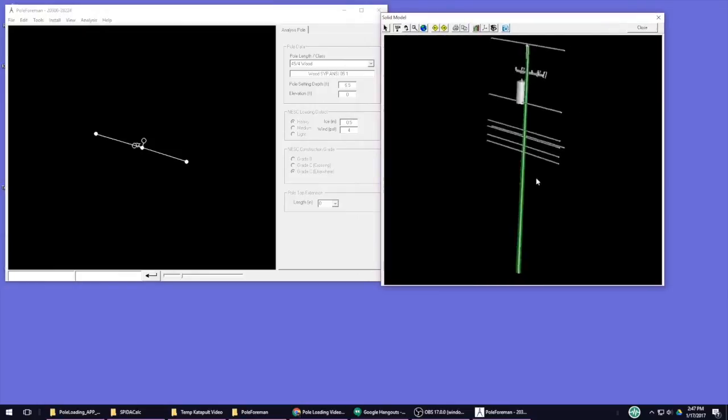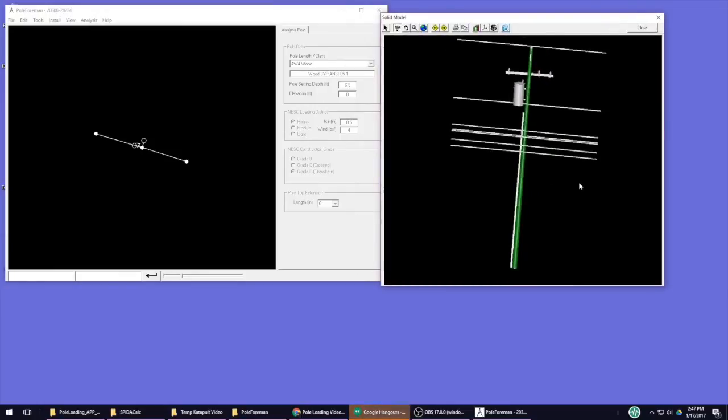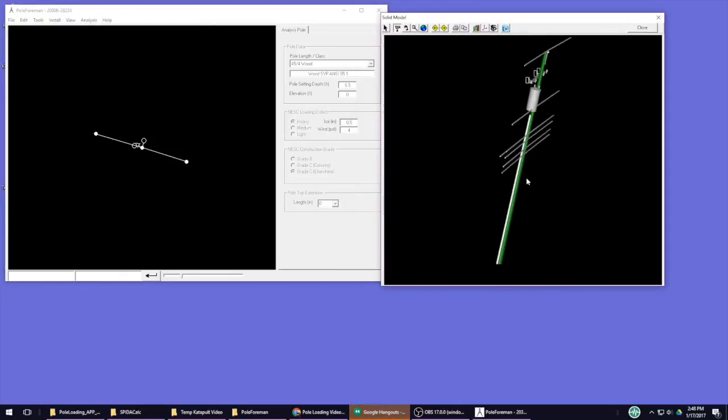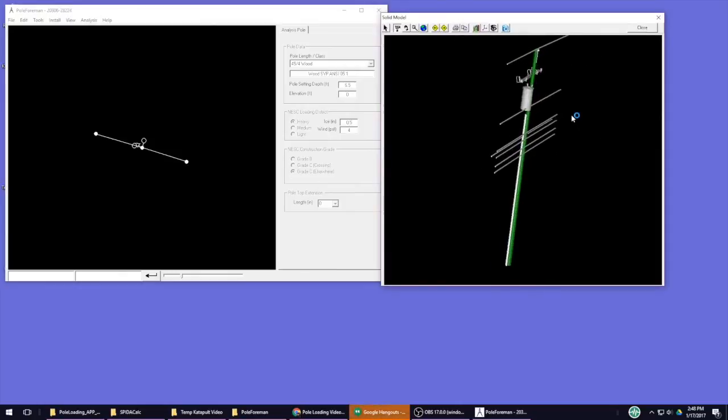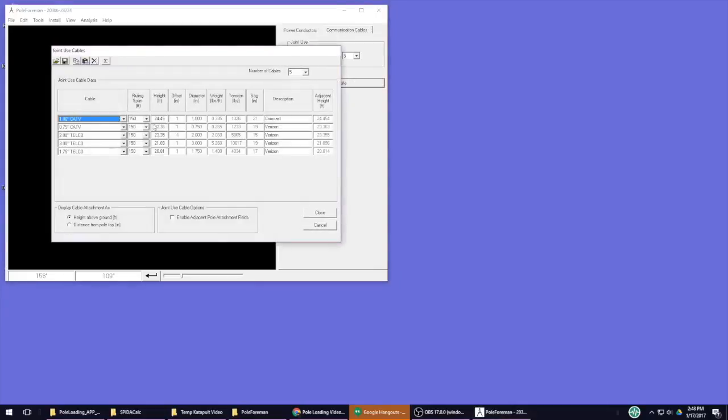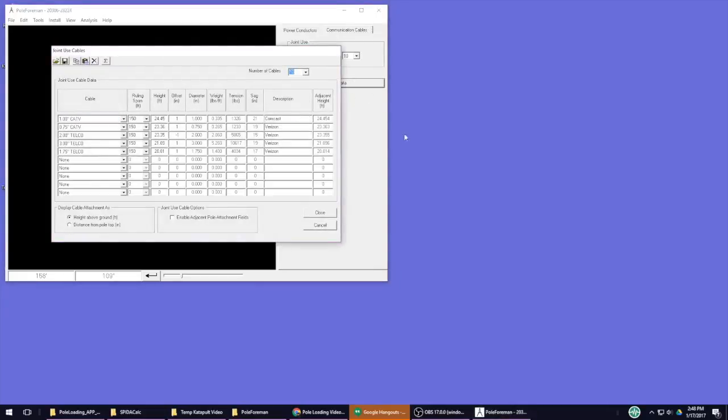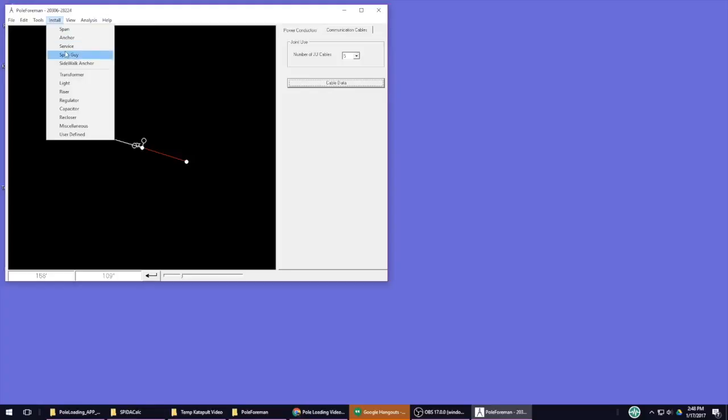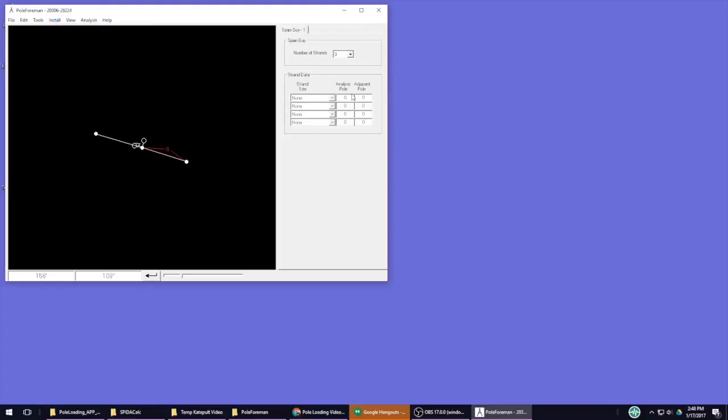Although the 3D model is great, the user cannot edit the pole and view the model at the same time. You have to alternate windows to see the visual edits you've made instead of being able to see them happen instantly. The biggest limitation I found in PoleForeman though, was its limit on cable and adjacent pole quantities. For example, you can only place 4 guys on a span.